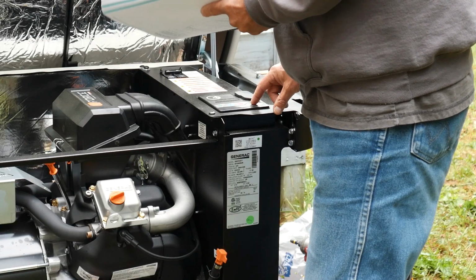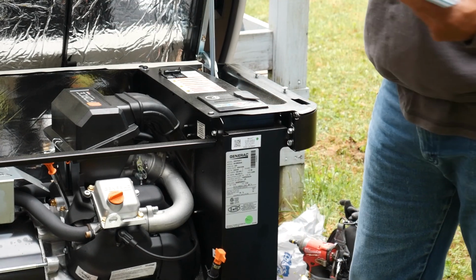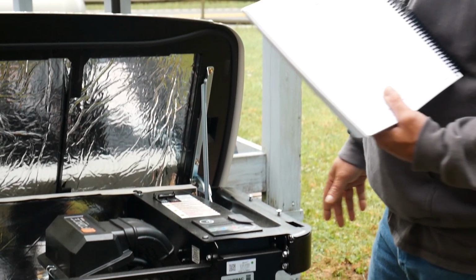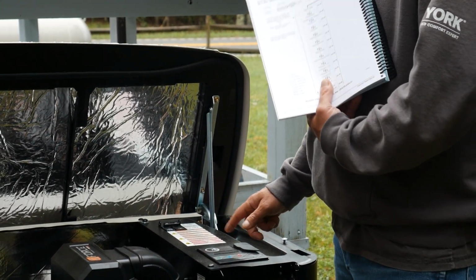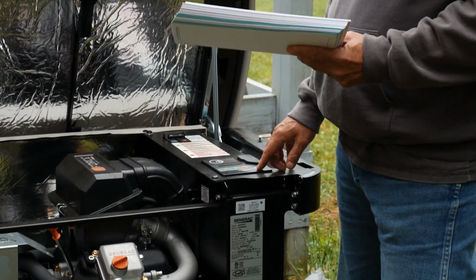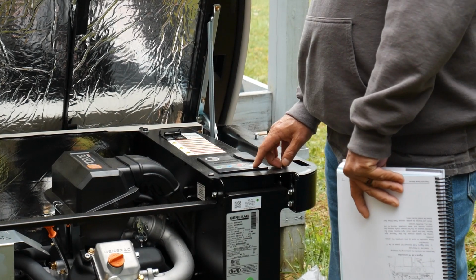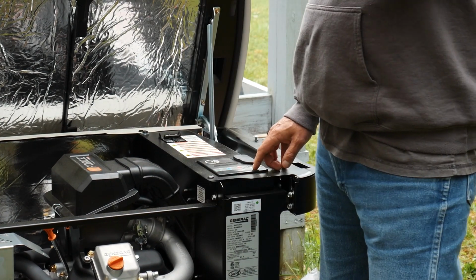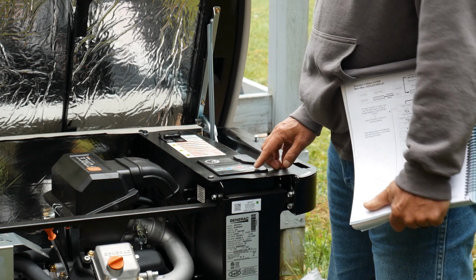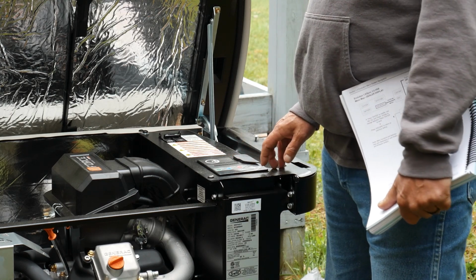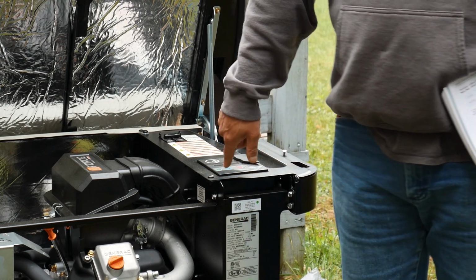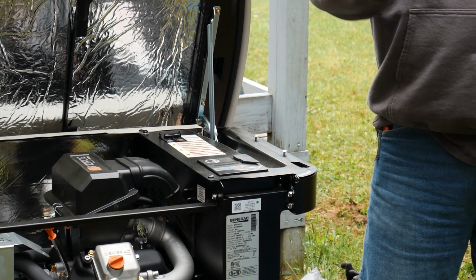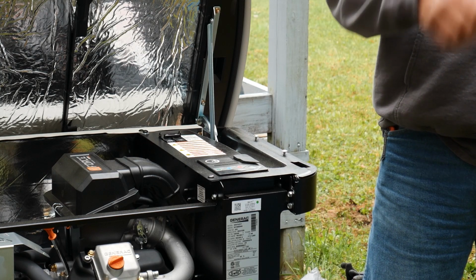Once you're in the display, whether it's running or not, you can go through your voltages. Right now the battery voltage is 13.9. Charging status shows it's charging because you have 110 coming into it. Run hours are at 24.5—you'll check your run hours and write that down on your work order in your notes.